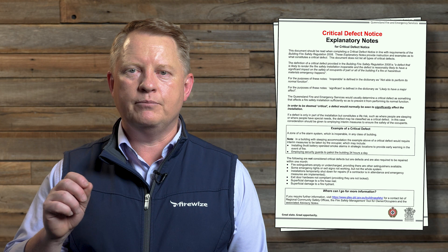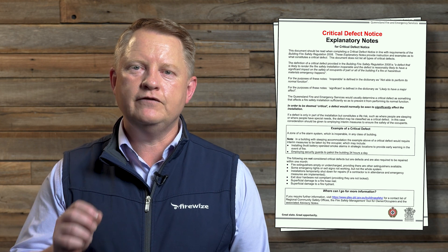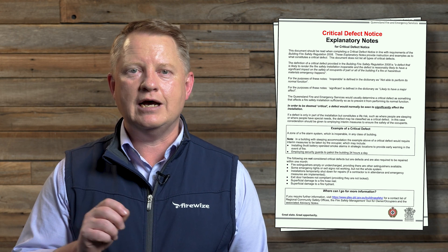If a person carrying out the maintenance of a prescribed fire safety installation becomes aware, or ought reasonably to be aware, of a critical defect in the installation, then they must give the occupier of the building a notice about the defect using an approved form called a critical defect notice. This form must be provided to the occupier within 24 hours after the maintenance activity has been performed.